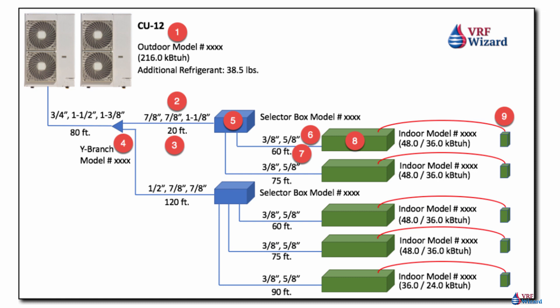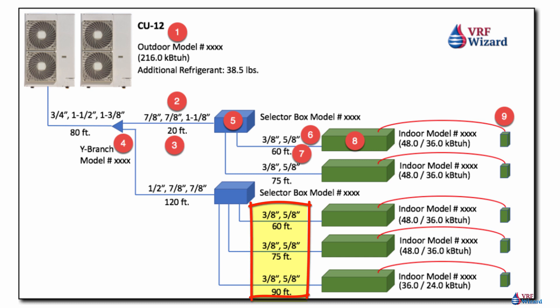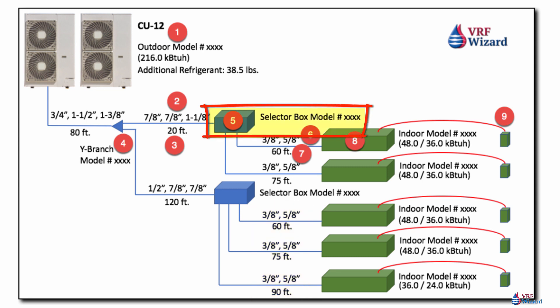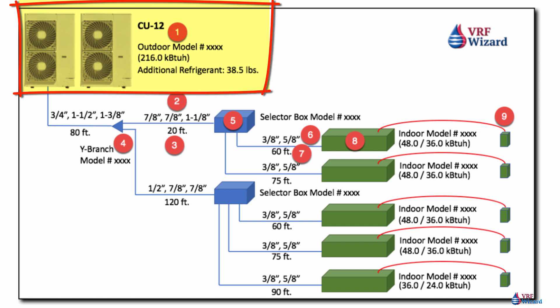The VRF design software will give you the following: indoor model numbers, thermostat or controller model numbers, pipe sizes — you input the length and it tells you what size you'll need. It will pick the branch selector box, which is for a heat recovery system. If you just have a heat pump, you won't have those. It will also give you the pipe size going to the outdoor units, and once you've selected all your indoor units, it will select the outdoor unit or give you options from various outdoor units.